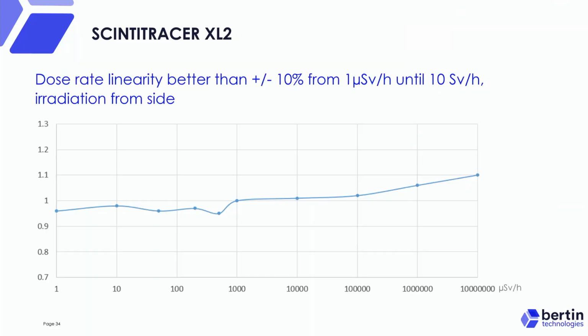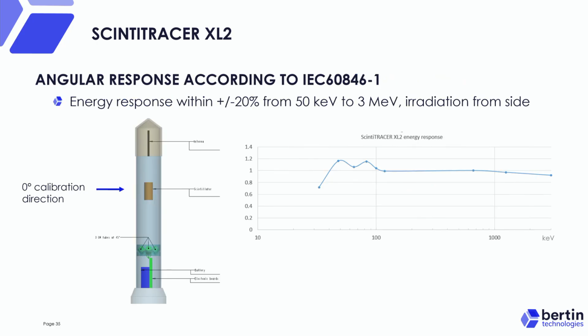There are a lot of requirements when we talk about such kinds of devices. And you see that from even 1 microsievert per hour to 10 sievert, we have ±10%. And the same situation when we talk about energy response. Energy response is also very important when we would like to have a measurement device according to the norms. You see here we made a test from 50 keV to 3 MeV, and the deviation is only ±20%, which is very good for such kinds of devices.